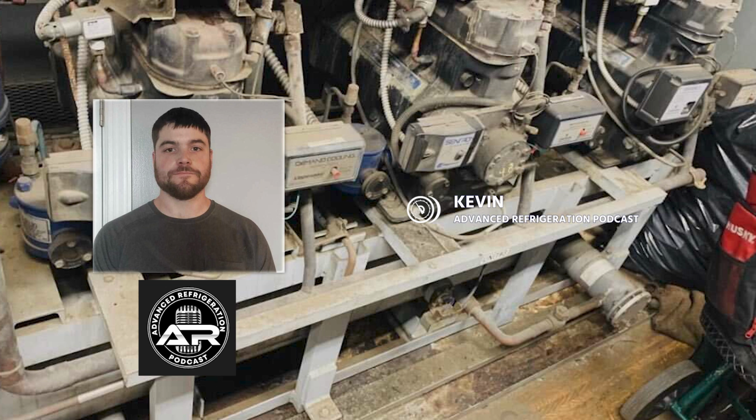Yeah, and that's another interesting thing, because in HVAC we'll talk about design temperature difference, DTD or TD, and we refer to that as the difference between the entering air temperature and the suction saturation. A common DTD would be 35, but in refrigeration they refer to it as the difference between the air returning to the box and the saturated suction. It's important that you get that distinction between the two. Otherwise you'll be like, what, 15, 35, what is it? Yeah. And some of ours, you see design temperature splits as low as, I was doing some cases this morning, they were 4 degrees.